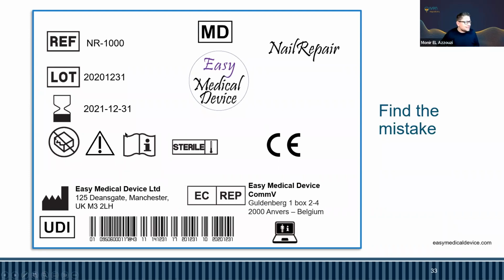So here it says that it's sterile. If it's a class 1 that is sterile, then there should be a notified body number here. If you see a label like that with a CE symbol and sterile, you say there is a mistake here. This manufacturer is not compliant. His product is not compliant to be on the market because he has placed it on the market as a class 1, but as it is sterile, he hasn't consulted the notified body, so it's not compliant to be on the market.